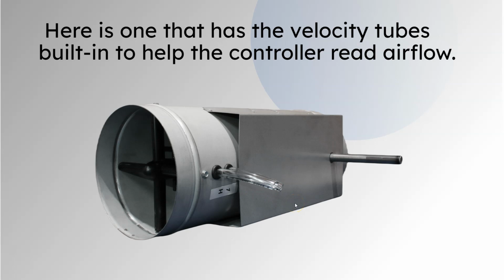Here's basically the same thing. It's just that this has a velocity tube in it, so it can pick up velocity pressure. A velocity tube is kind of like a pitot tube, sort of. We've got holes on one side. This is the side facing the air handler. And as the air comes down, it's going to go through those holes at a higher pressure than the holes on the backside. There's a high tube and a low tube. The high is the one facing the air handler. The low is the one facing away from it. So as the air pushes on it, there's going to be more high pressure than low pressure.